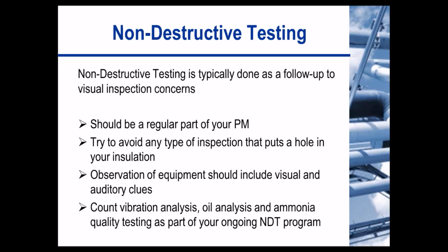So non-destructive testing isn't completely included in the B109 checklist, but it is included here as a follow-up to the visual inspection concerns. And it should be a part of your preventive maintenance. Try to avoid any type of inspection that puts a hole in your insulation. Observation of equipment should include visual and auditory clues. Count vibration analysis, oil analysis, and ammonia quality testing as part of your ongoing non-destructive testing.